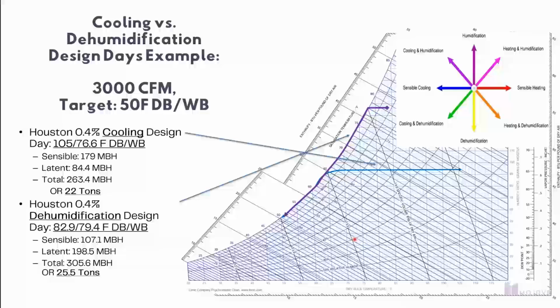So, quick example from a design perspective. One thing I've seen a lot out there is a lot of engineers only look at a cooling design day or specify only a cooling design day for their DOAS and dehumidification applications. I would encourage design engineers to review not only your cooling design day, but your dehumidification design day as well. And the reason for that is typically the enthalpy on a dehumidification design day is actually higher than your enthalpy on a cooling design day. So even though it's not as hot, quote unquote, outside, there's a lot more moisture content in the air.